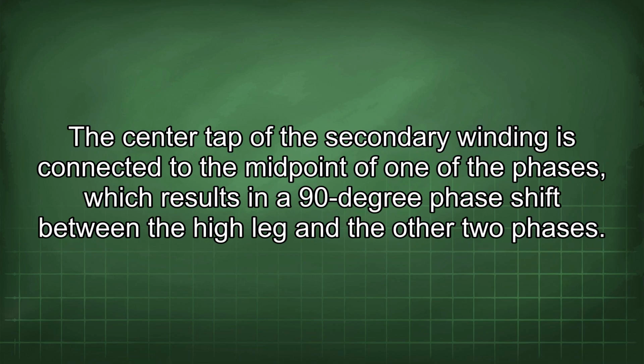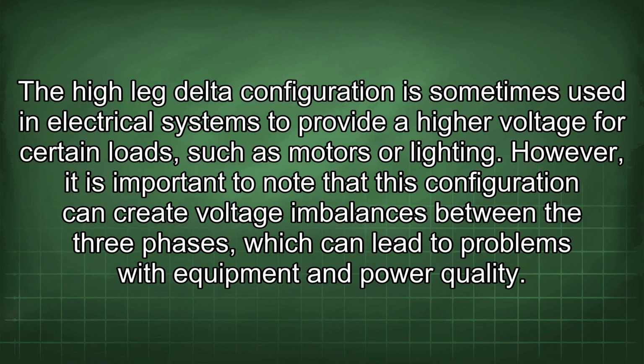The center tap of the secondary winding is connected to the midpoint of one of the phases, which results in a 90-degree phase shift between the high leg and the other two phases. The high leg delta configuration is sometimes used in electrical systems to provide a higher voltage for certain loads, such as motors or lighting. However, it is important to note that this configuration can create voltage imbalances between the three phases, which can lead to problems with equipment and power quality.